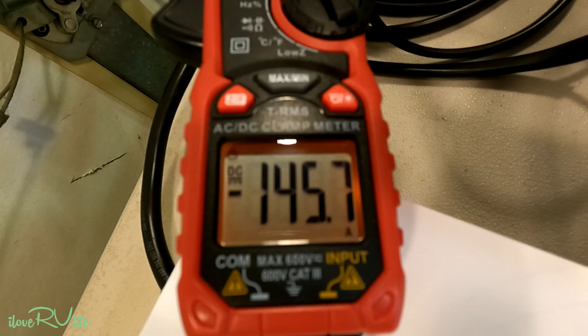Boom, we went to 1650. We're at 145, I just heard the fan cut on, and there it went. So that shows you the BMS does work within an overload, and it can handle a short duration surge for any type of device. This went up to about 145 amps and probably held at maybe 3 to 4 seconds thereabouts before it wasn't the inverter that shut off, the BMS then shut off, and you just have to power your device down and power it back up.